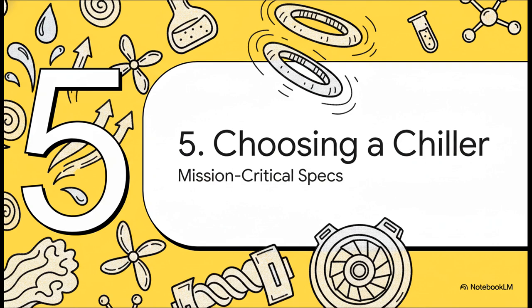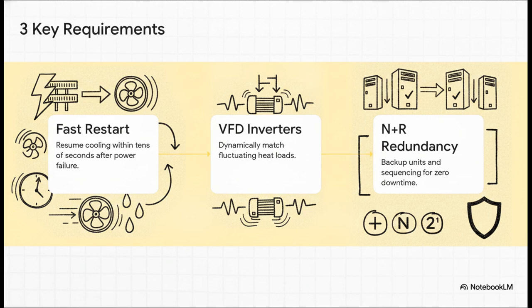All right, our final section, Section 5, how to choose a chiller. With all these options out there, how does a facility actually choose? Well, operators have to meet 3 mission-critical requirements. First, fast restart. If the power fails, the chiller must recover and resume cooling within tens of seconds after the generator kicks in. Second, VFD inverters. The compressor must adjust its frequency dynamically to match the constantly fluctuating heat loads of AI servers. And third, N+R redundancy. You absolutely must have precise sequencing and backup units, like N+1 or 2N configurations, to ensure zero downtime. Because honestly, even one single second of cooling failure can take an entire network offline.